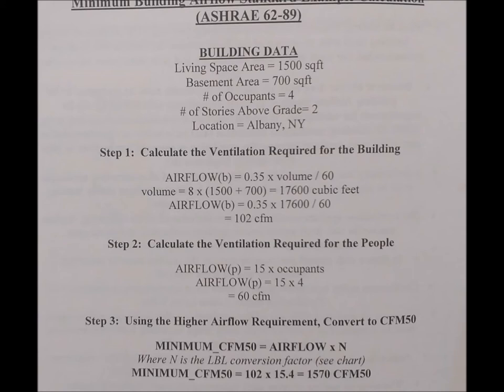Minimum Building Airflow Standard Example Calculation. Building data: Living Space Area equals 1,500 square feet; Basement Area equals 700 square feet; Number of Occupants equals 4; Number of Stories Above Grade equals 2; Location: Albany, New York. Step 1: Calculate the ventilation required for the building. Airflow B equals 0.35 times volume divided by 60.